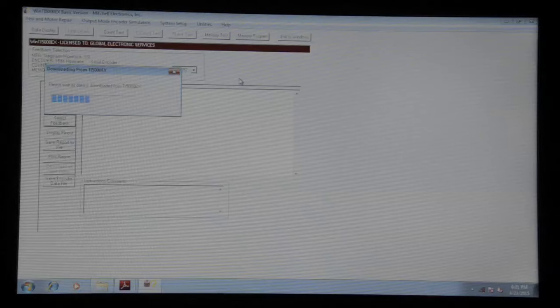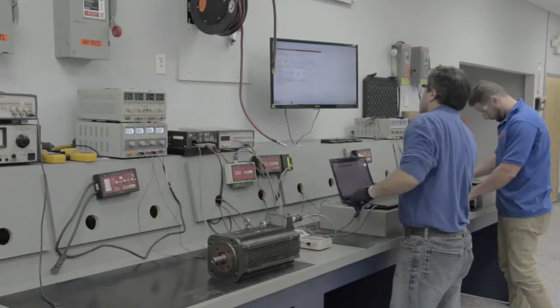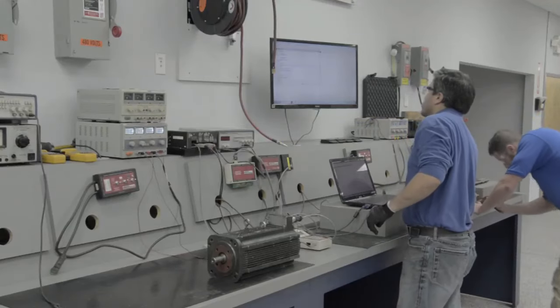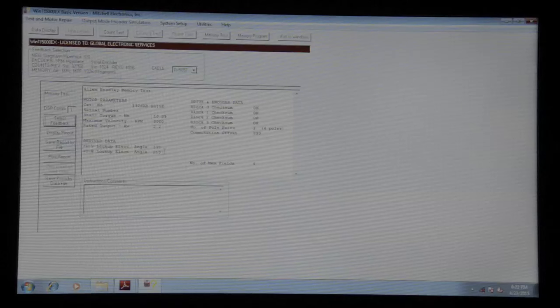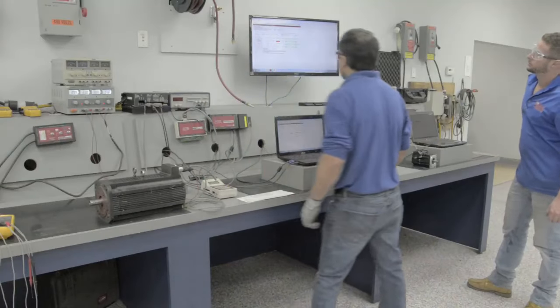This shows us all the information about the motor and that the angle U to V is 199 degrees and U to W is 259 degrees. We'll verify by entering poles and lock-up angles. Set the U to V angle to 199 degrees and test. We will repeat this step for the U to W angle.